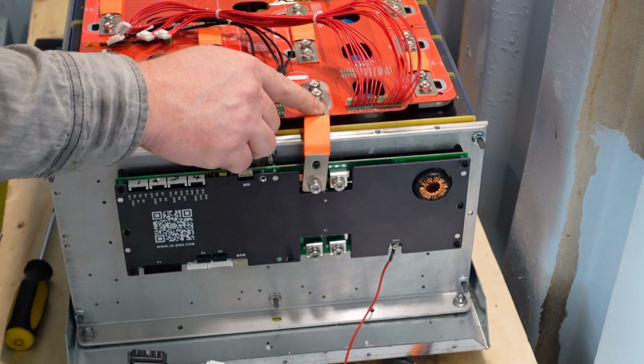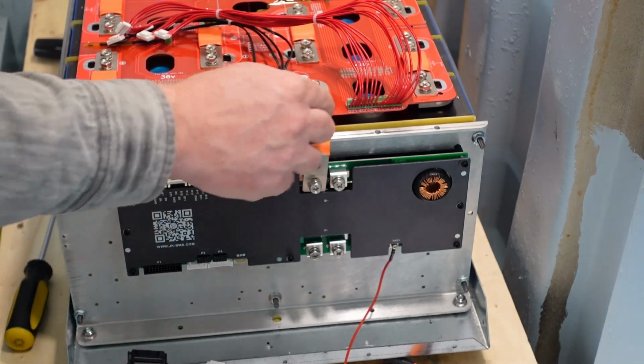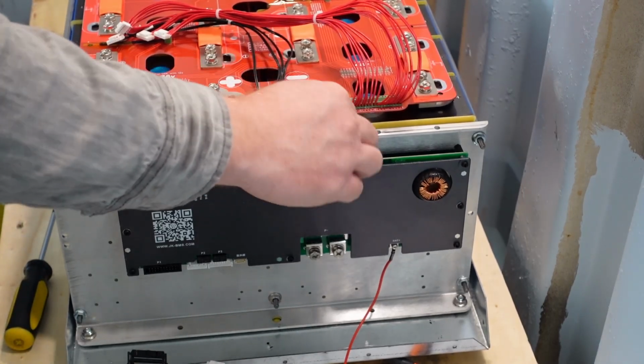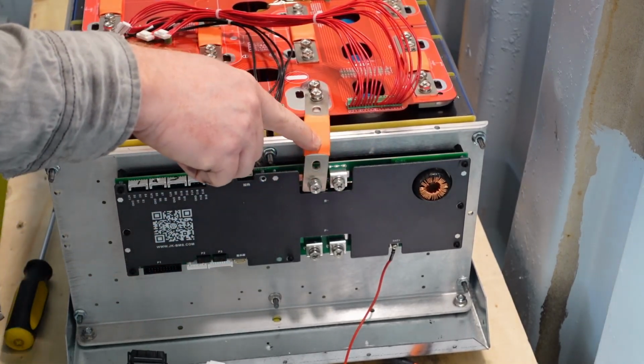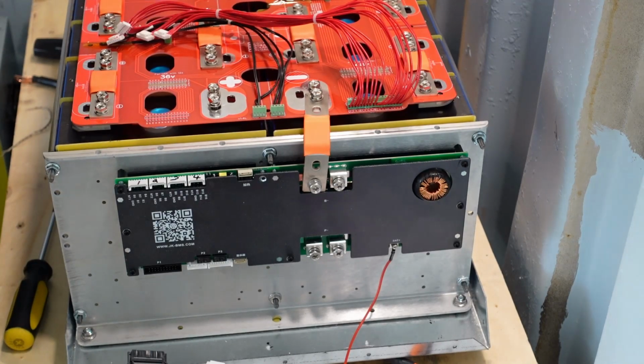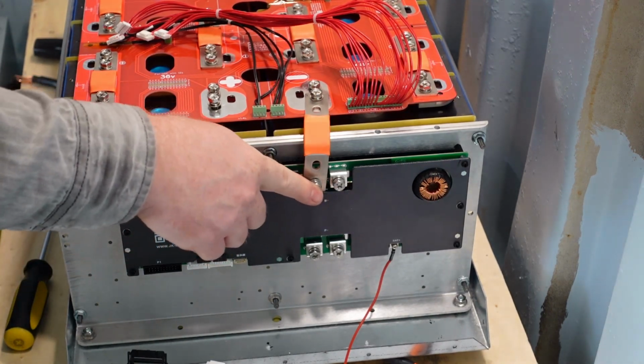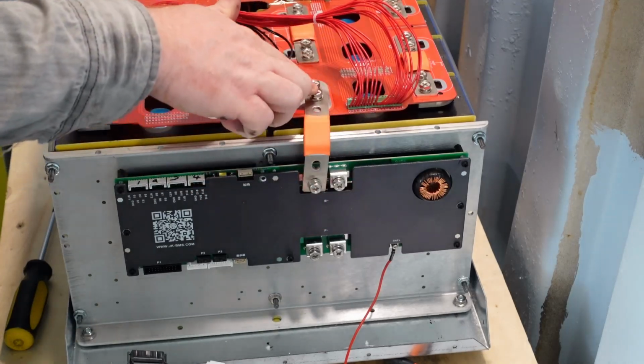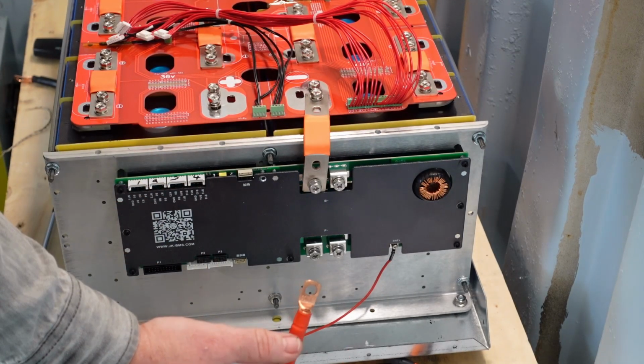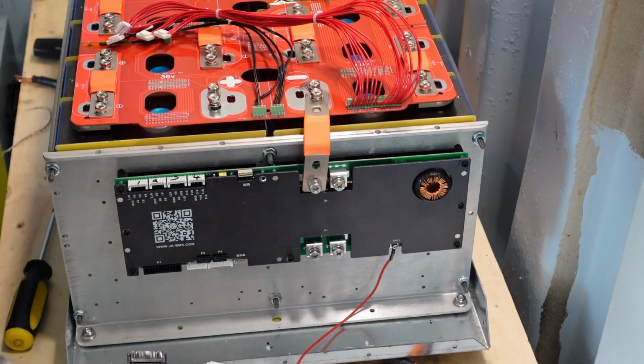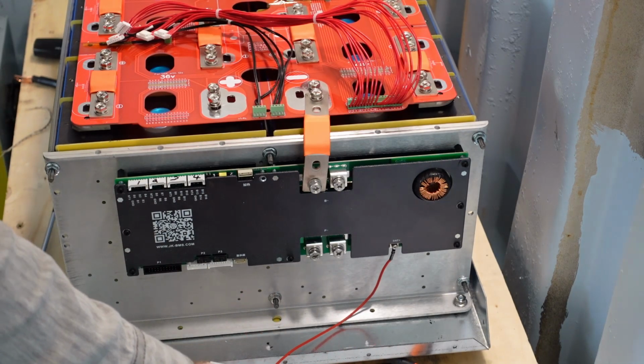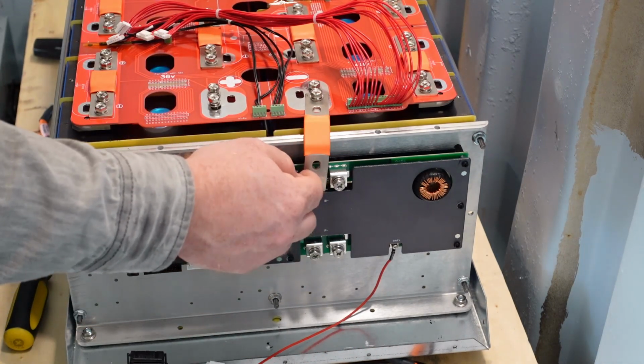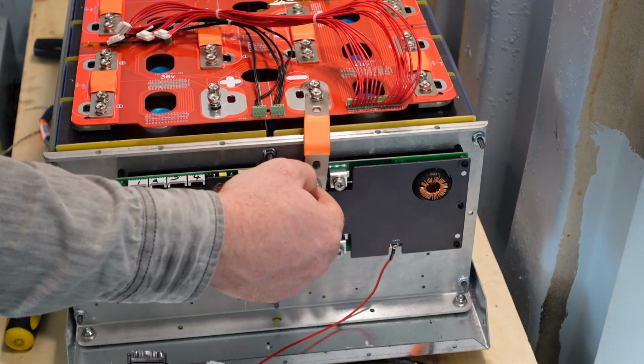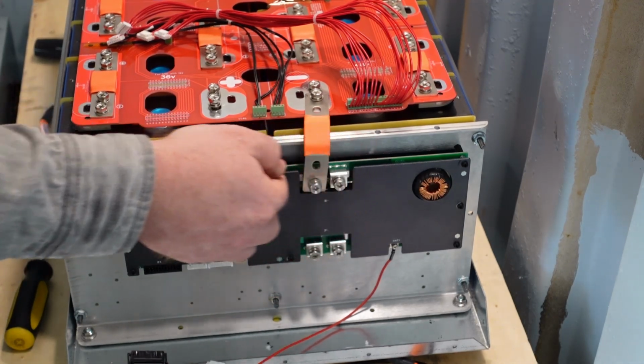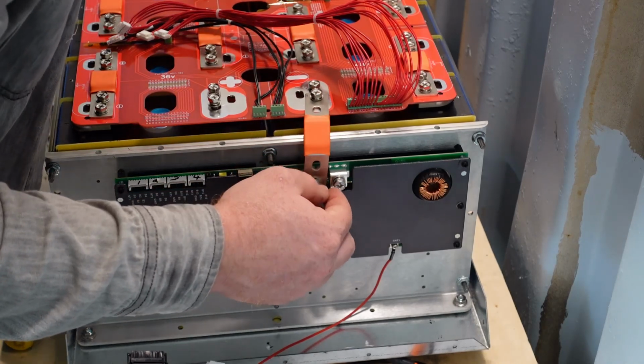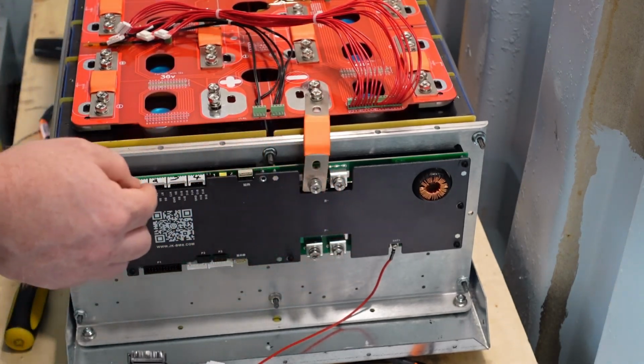So I don't know, I kind of like this. It's stiff enough that it won't come into contact, it's already insulated, and I know it's rated for 200 amps. Kind of novel. But the proper gauge wire, if you wanted to use 2 of them, would be 2 6-gauge wires, and this should be a 2 gauge or greater. Ideally if it was 4 gauge it would probably be fine. The only thing is, there are 2 terminals here meant to share the 200 amp load, and I don't know if one of them by itself is designed to handle the full 200 amp.